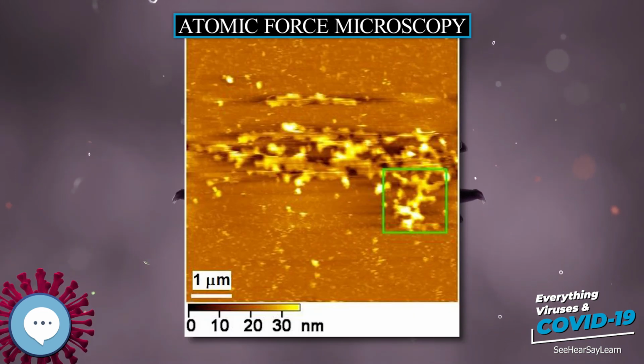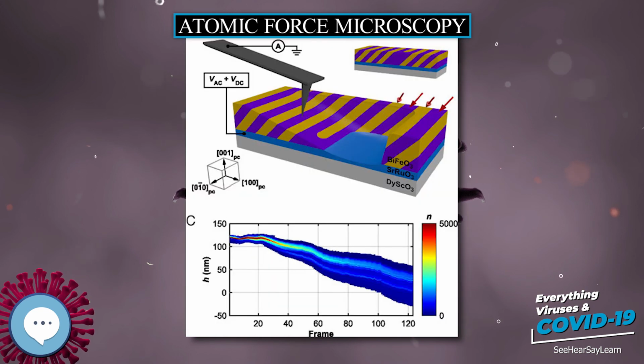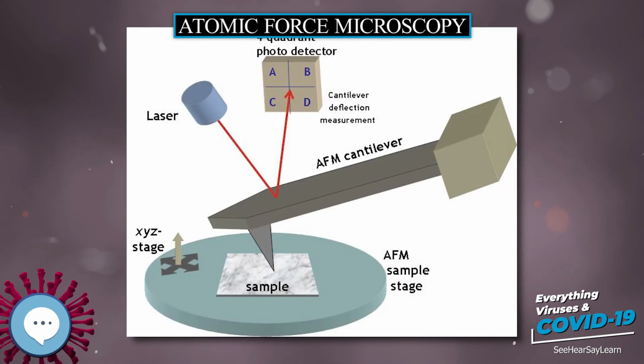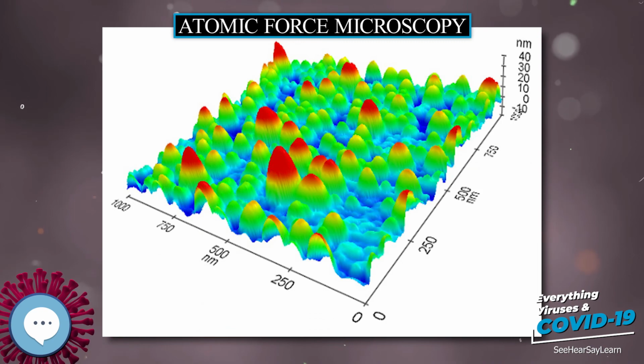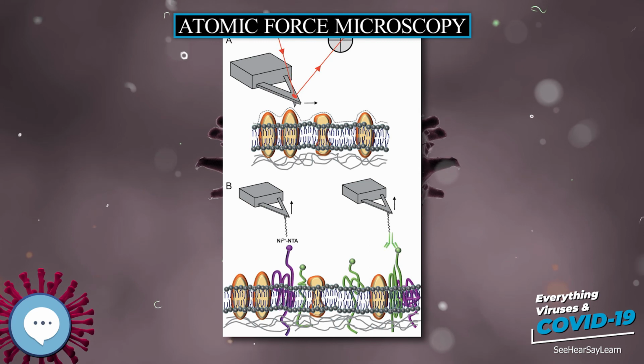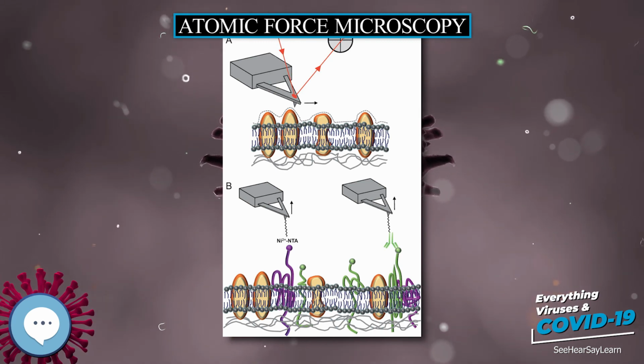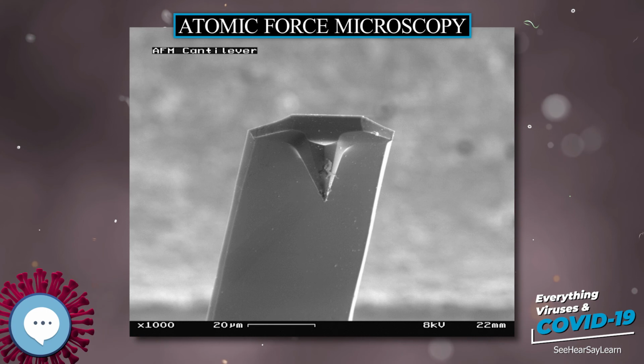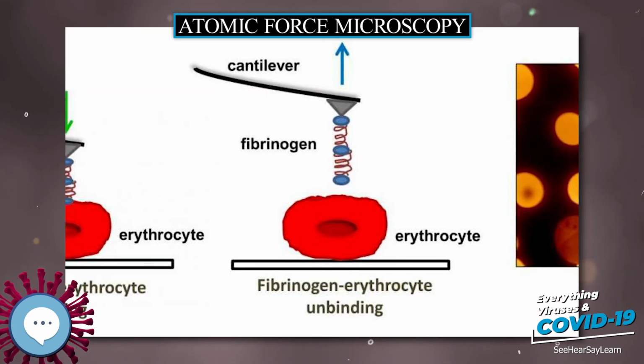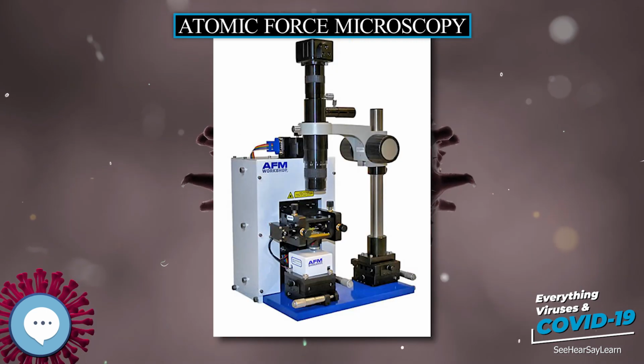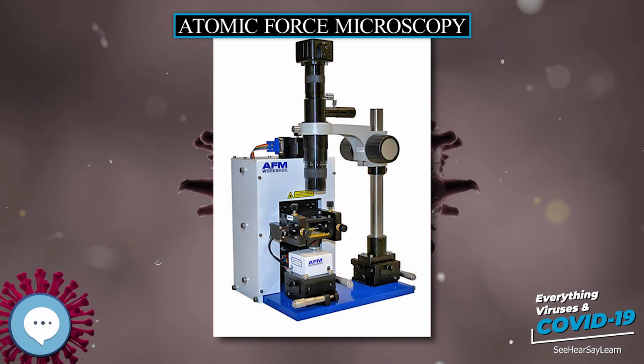When the distance between the probe and the sample is brought to the range where atomic force may be detected, while a cantilever is excited at its natural eigenfrequency, f0, a phenomenon occurs in which the resonance frequency, f, of the cantilever shifts from its original resonance frequency, the natural eigenfrequency. In other words, in the range where atomic force may be detected, the frequency shift, df equals f minus f0, will be observed. So, when the distance between the probe and the sample is in the non-contact region, the frequency shift increases in the negative direction as the distance between the probe and the sample gets smaller.